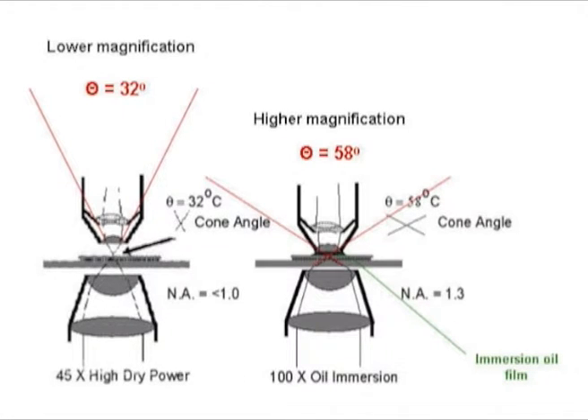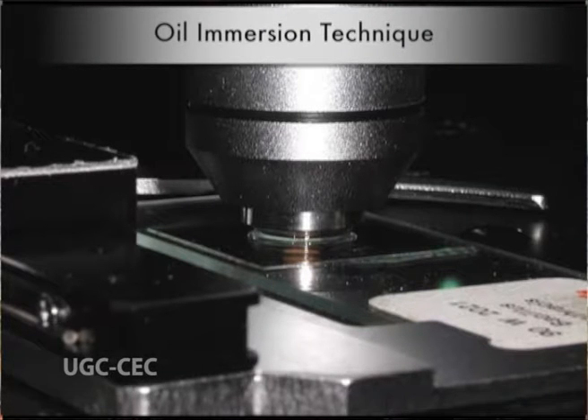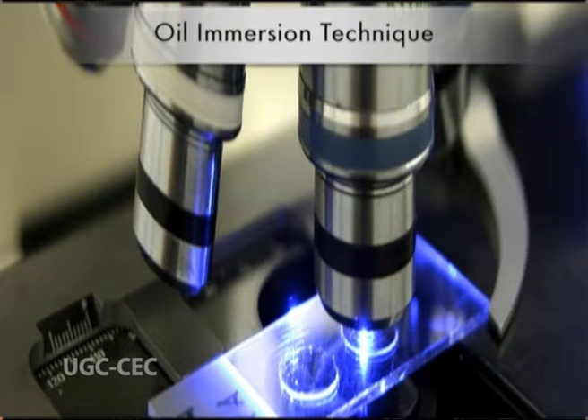Most microscope slides and cover slips have refractive indexes of 1.5, whereas air has a refractive index of 1. When light passes from one medium to another, say from glass to air, it refracts or bends and scatters. If we use a dry objective, the light rays from the specimen will undergo refraction when travelling from the glass cover slip into the air. The refracted rays are not usually collected by the objective front lens and are lost from the final image. If we use an oil immersion medium to replace the air gap, we can correct this mismatch.